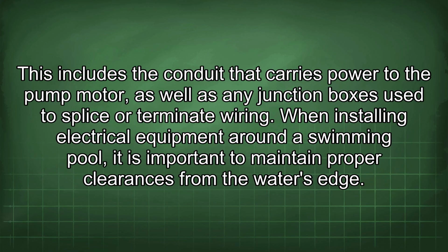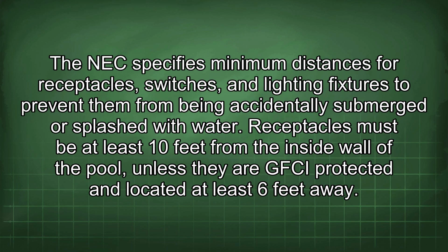This includes the conduit that carries power to the pump motor, as well as any junction boxes used to splice or terminate wiring. When installing electrical equipment around a swimming pool, it is important to maintain proper clearances from the water's edge. The NEC specifies minimum distances for receptacles, switches, and lighting fixtures to prevent them from being accidentally submerged or splashed with water. Receptacles must be at least 10 feet from the inside wall of the pool, unless they are GFCI protected and located at least 6 feet away.